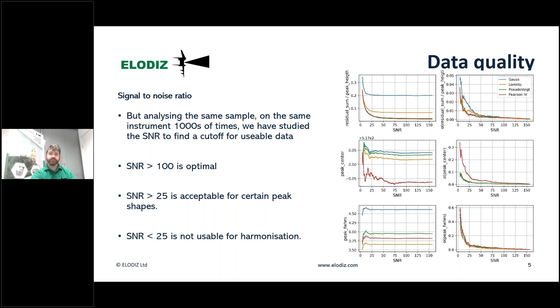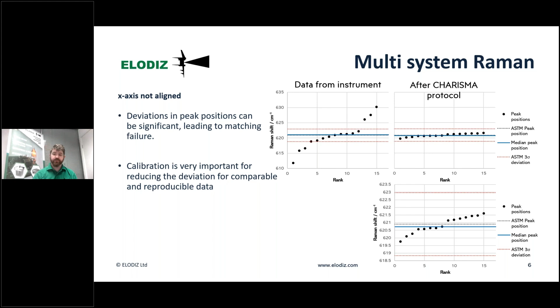So this kind of expands on what Enrique was showing, where he was showing you the data that comes from instruments as they are currently installed in different laboratories and different industry placements, and how we get a wide range of peak positions for a peak that should be at 620.9 according to the current existing standards. And as you can see, after using our Charisma protocol to perform a calibration adjustment or a recalibration, as you wish to call it, all of the different systems have that peak within the anticipated range that it should be, allowing for comparisons to be made better between different instruments.